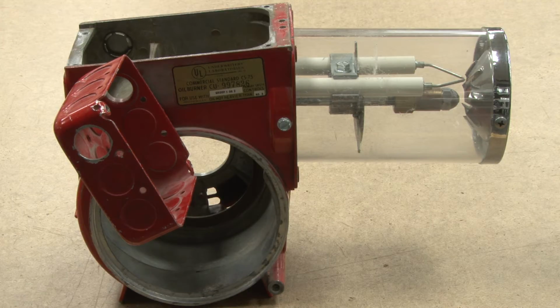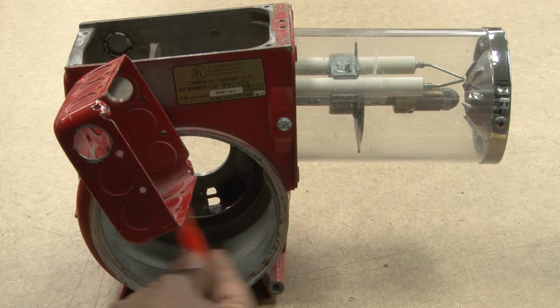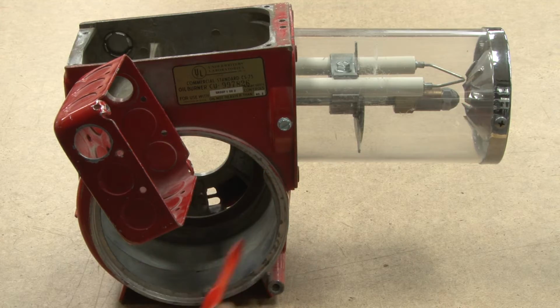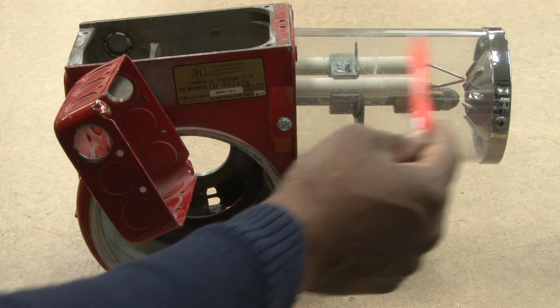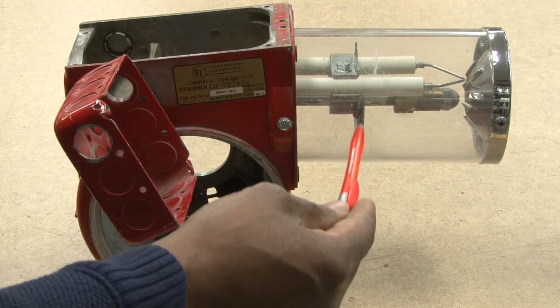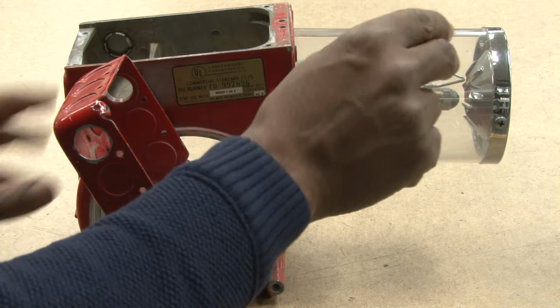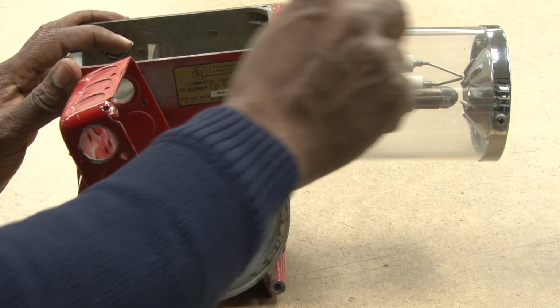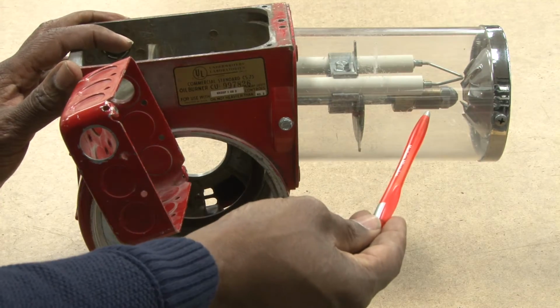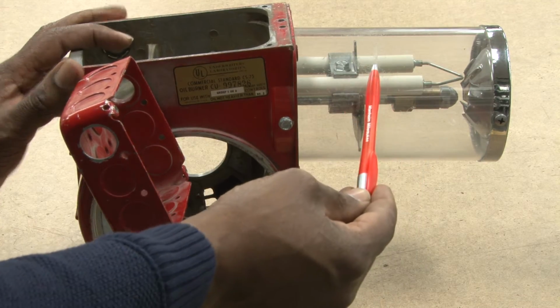In this video, we'll show the individual components of the oil burner, and it's kind of neat because we have a cutaway of the oil burner so you can see the components, how they fit inside of the complete burner assembly. This is the blower assembly in this area here, where the blower will be connected. But in this burner tube, it's clear, so you'll be able to see the electrodes and the oil tube with the nozzle. The nozzle at the bottom, the electrodes at the top.